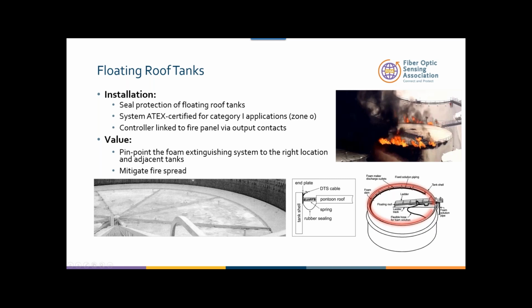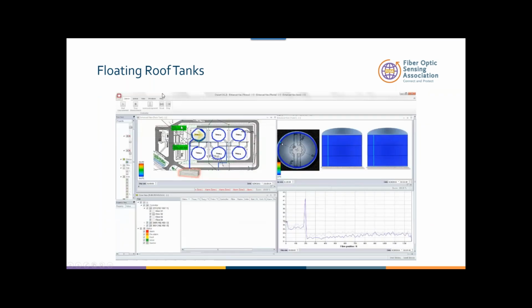So the ability to put a fiber optic linear detection cable on the roof tank and understanding where exactly, pinpoint, that it's coming from the left side, right side, or if you look at the quadrant system, you can actually activate the foam, which is a very, very expensive system, at the right location or flood the entire tank.